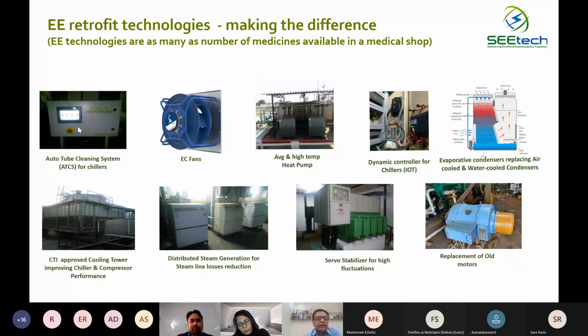So that deposition keeps taking place, and the heat transfer gets lower and lower. We have to continuously clean them. The moment you clean it, you will find a reduction in the condensing pressure on your vapor compression side. But that is a one-time process — then again it is done after 6 months or after 3 months.